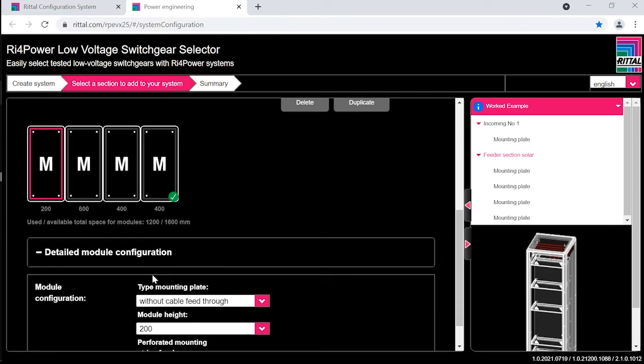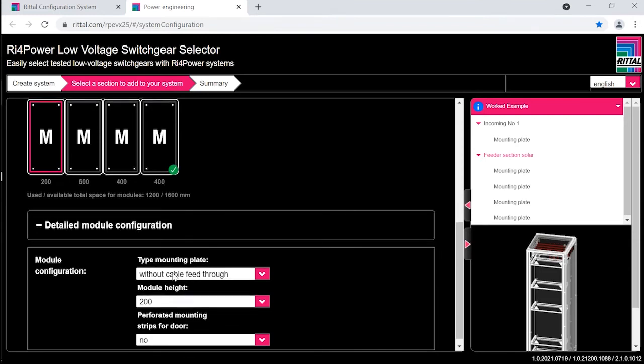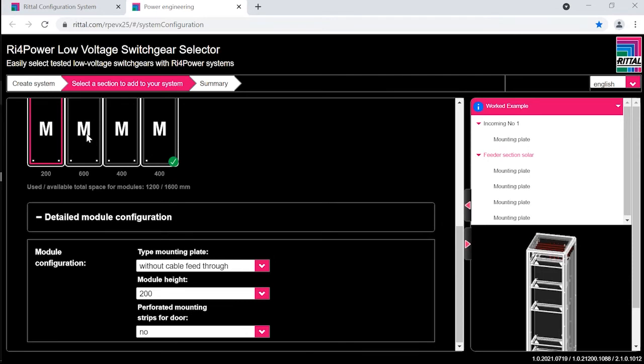So I mentioned previously about referencing our manuals, our technical guides. On there, it will show you that a 125 amp circuit breaker fits in a 200mm high compartment. A 400 amp circuit breaker will require a 300mm high compartment as a minimum. And this project has 10 125 amps, 4 400s. So split it 50-50. So in this enclosure there, it will need 5 200mm high enclosures. So that is 1. So we change that 600 door to a 200, and it gives you more options as you go further down this selection.